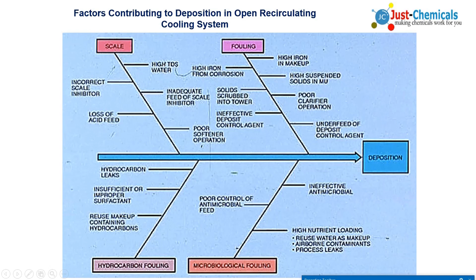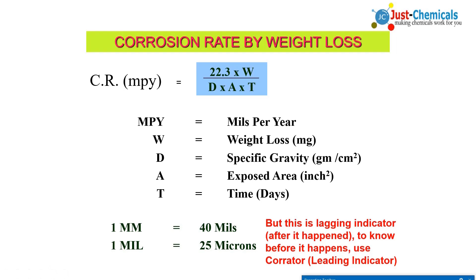Fourth, corrosion is measured in mils per year. 1 mil is 1 by 1000 inch, or 1 mil is equal to 25 micron, or 1 mm is equal to 40 mils. But again in red I have written here, you see, it is a lagging indicator, after it has happened. To know before it happens, use a corrator as a leading indicator. Corrator or corrosion meter, these are available in the market, you can purchase it.